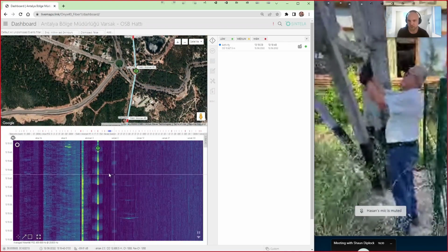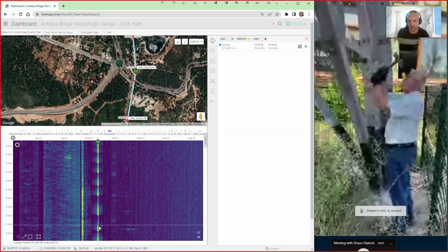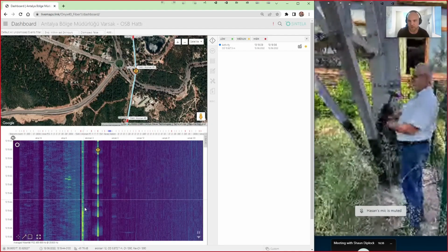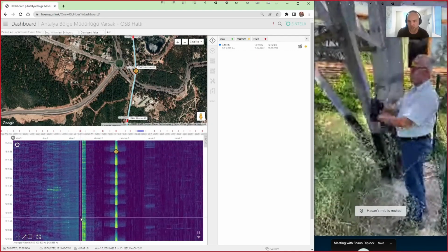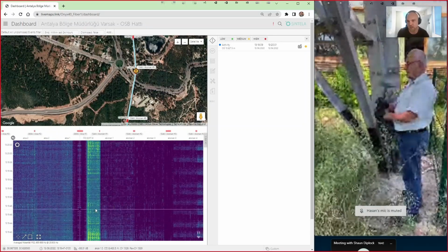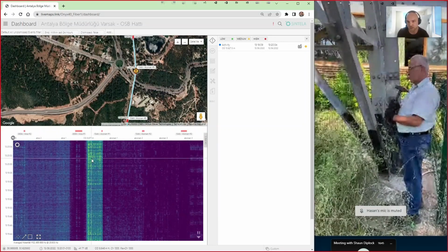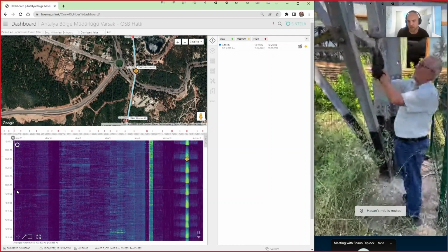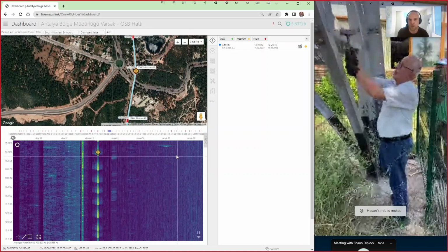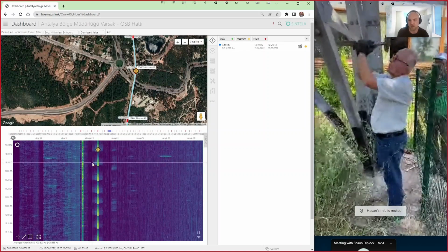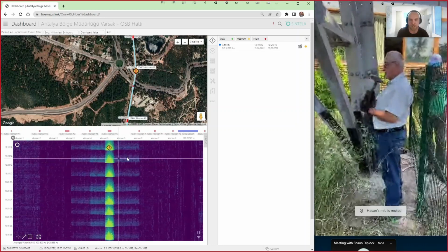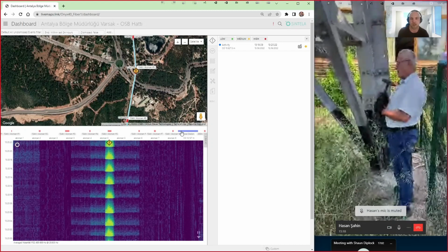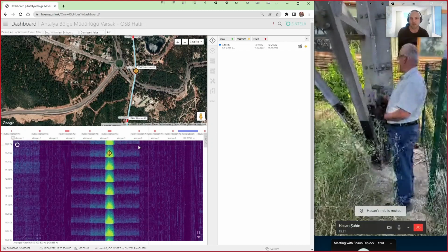Yeah, it's pretty cool. And so we can clearly see this activity here on the waterfall. We have some other noise on the waterfall. This is from wind, but as you can see, the wind noise is not causing alerts or false alerts. Right. We have some other background noise over here, but these are from unrelated events. The only thing causing alerts on the system at the moment is the activity of our field team here on the right-hand side hitting the pylon lightly with a hammer.